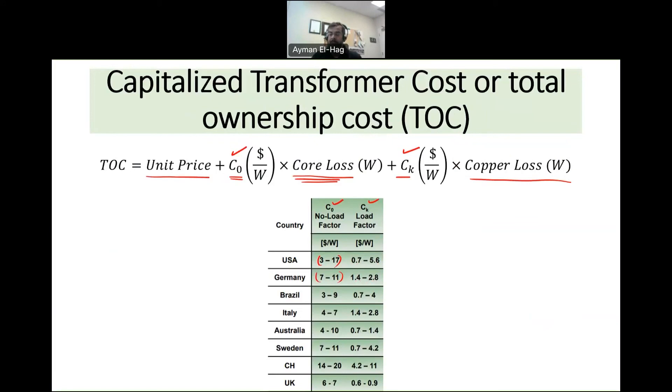So it's clear now we understand that when we buy the transformer the core loss is very important for the long term because it is 24/7. But the copper loss also is important and we consider it also in this capitalized formula. However, the factor we use to multiply the copper loss to calculate the cost should be much less than the factor we use to multiply the core loss.